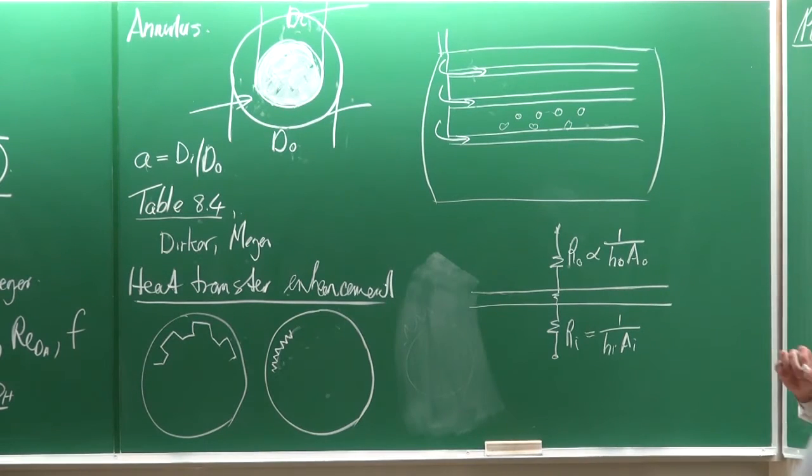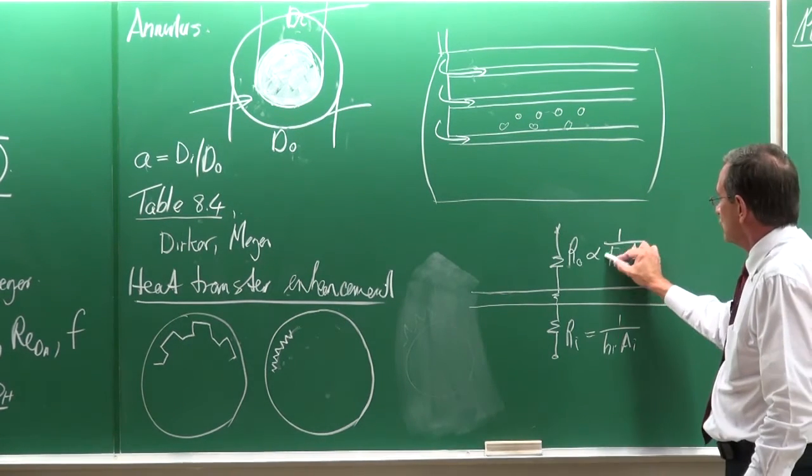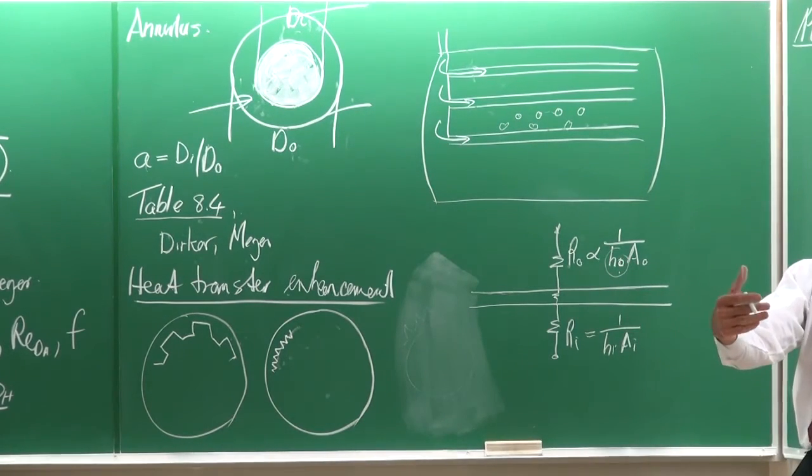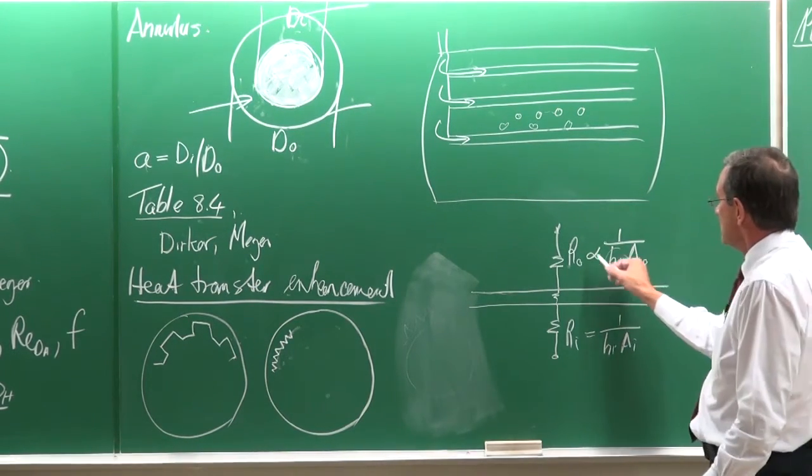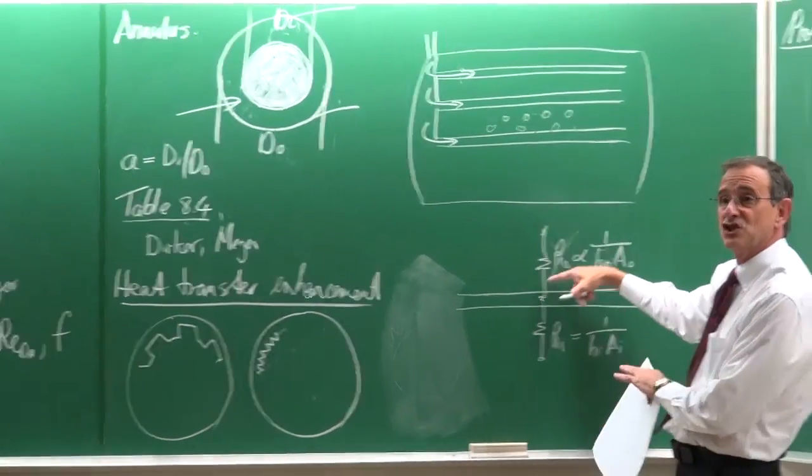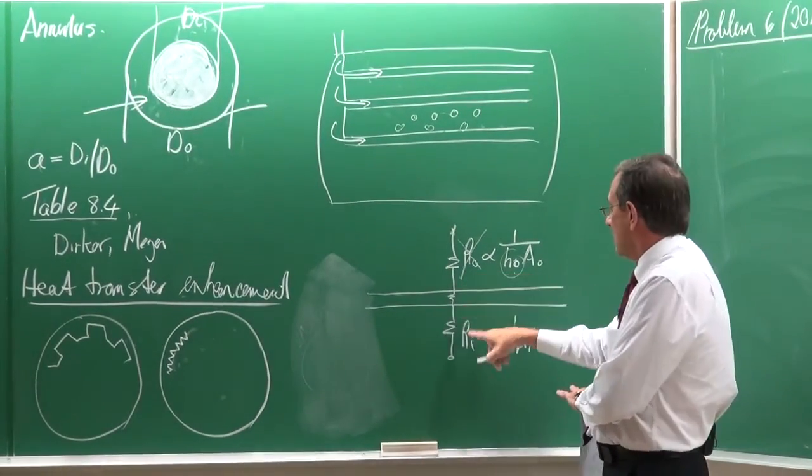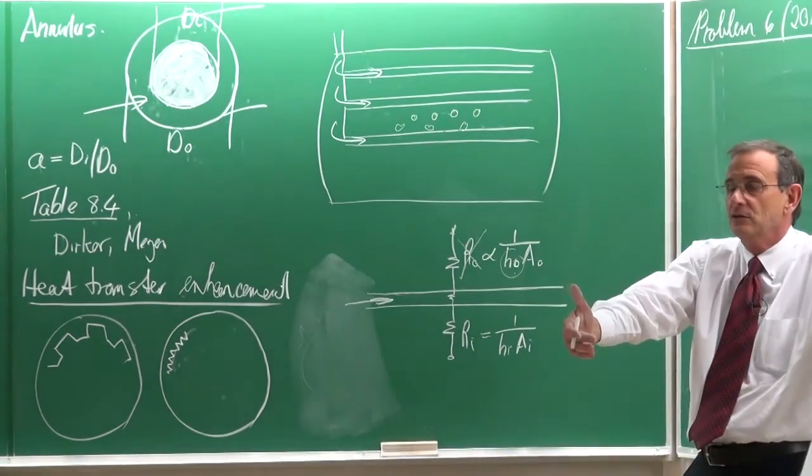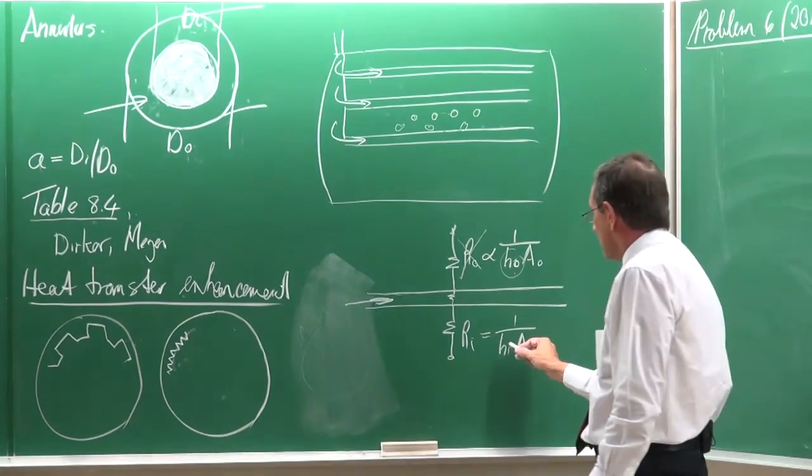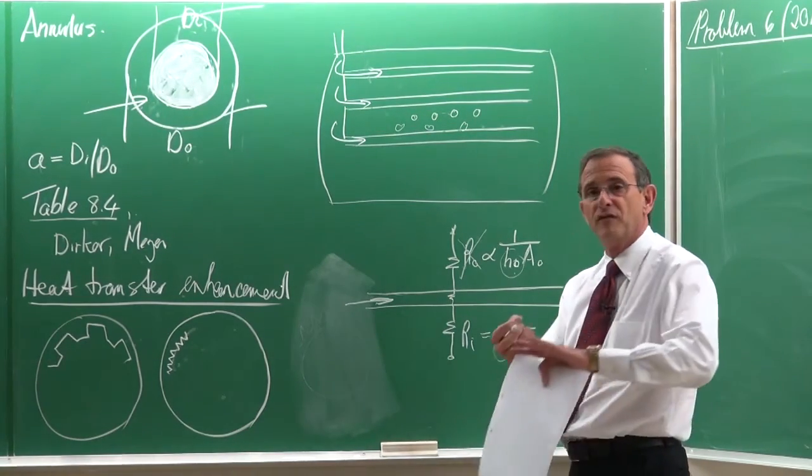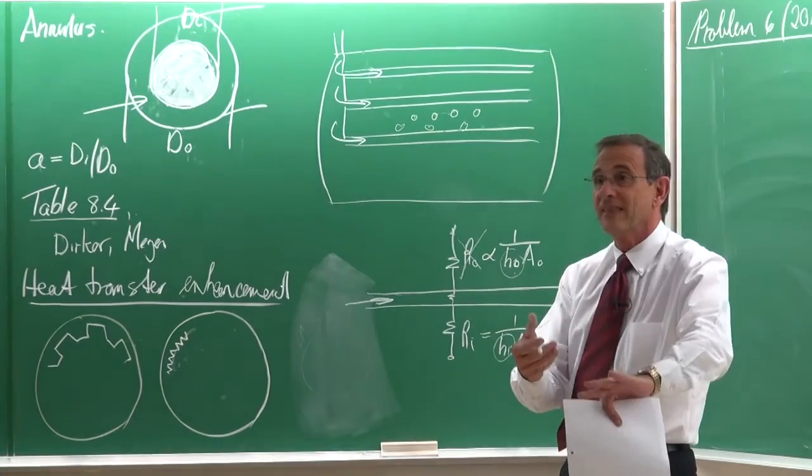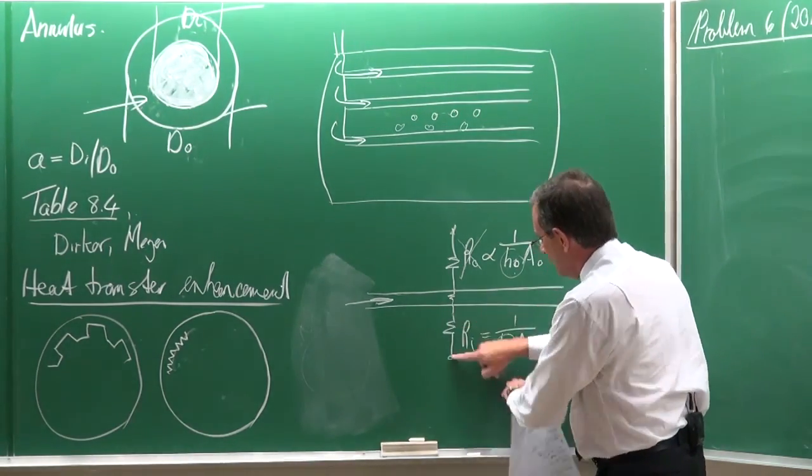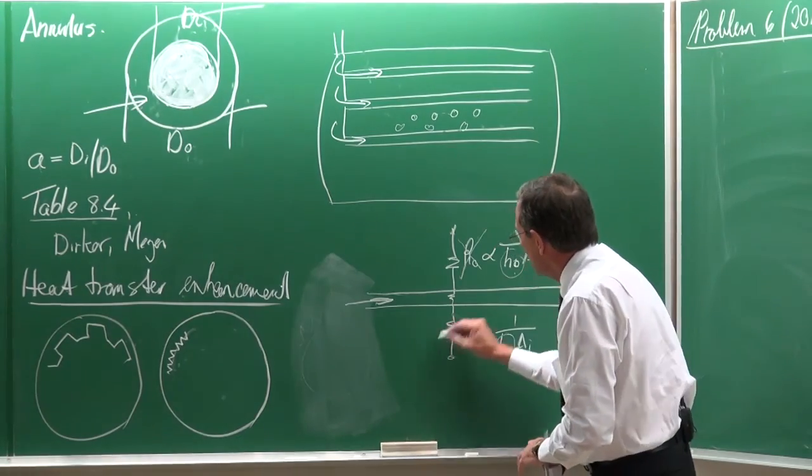boiling. Now, if you have boiling then the heat transfer coefficient is in the order of magnitudes of tens of thousands. 10,000, 20,000, 30,000. It means that this resistance is extremely small. And here you will have water. So, typically in a chiller you cool water from 20 to 10 degrees. And this heat transfer coefficient is of a single phase fluid. So, typically order of magnitude 1,000. So, if you look at this problem then you will see most of the resistance is actually on the inside of the tube.